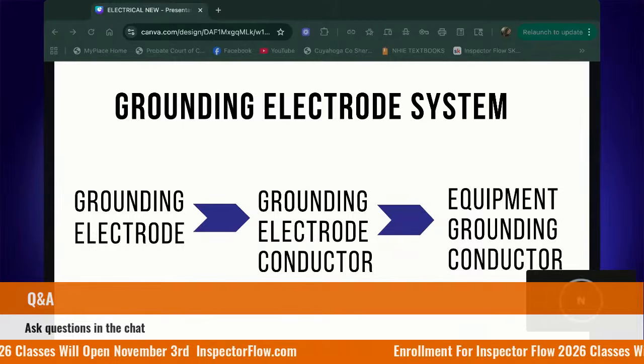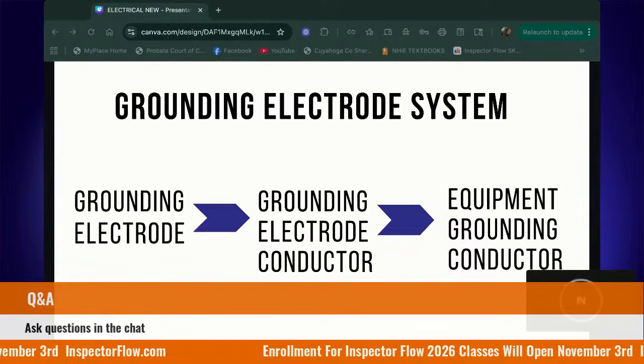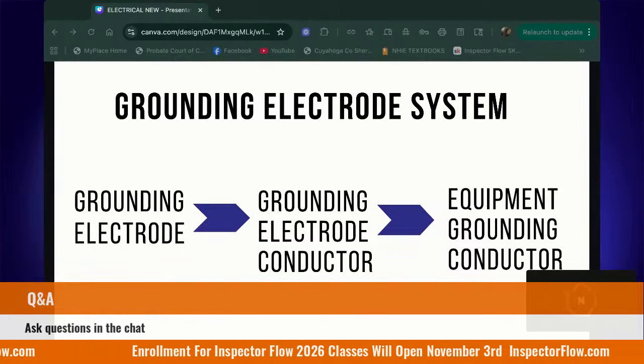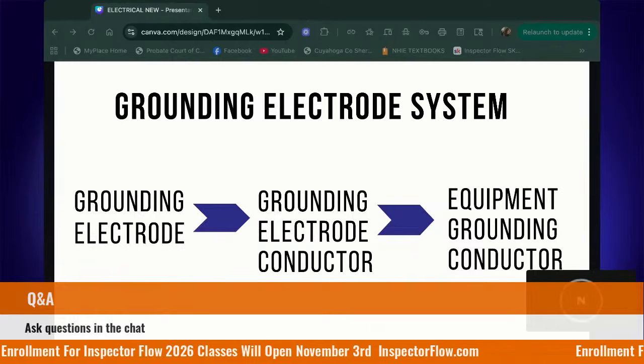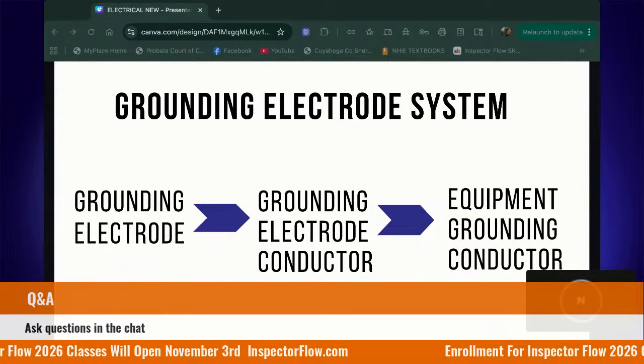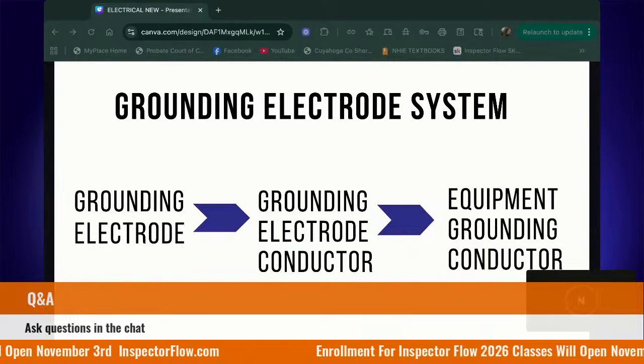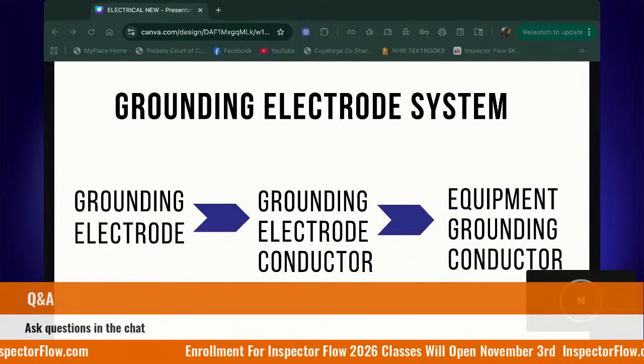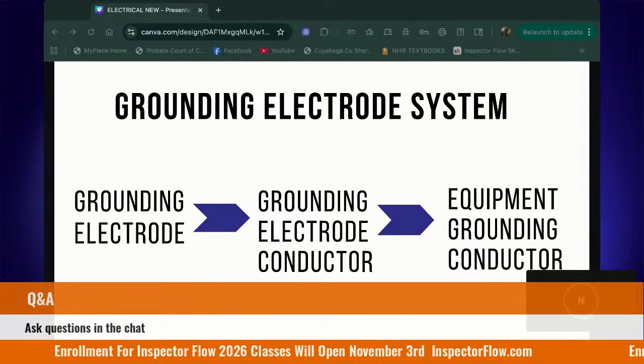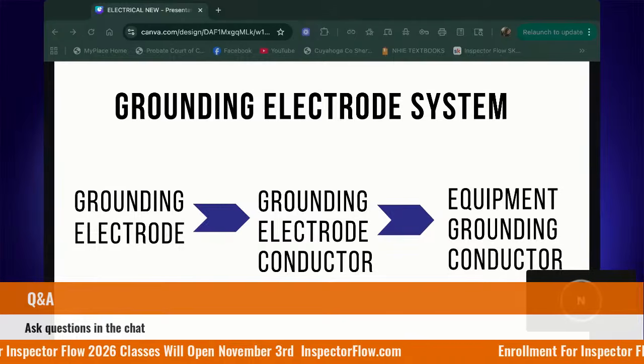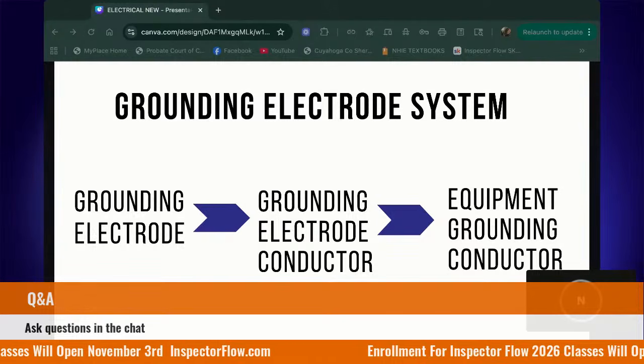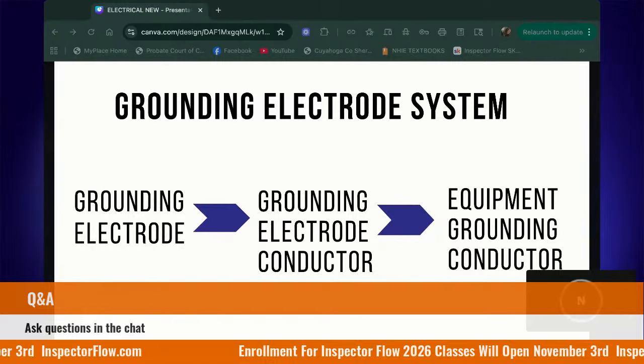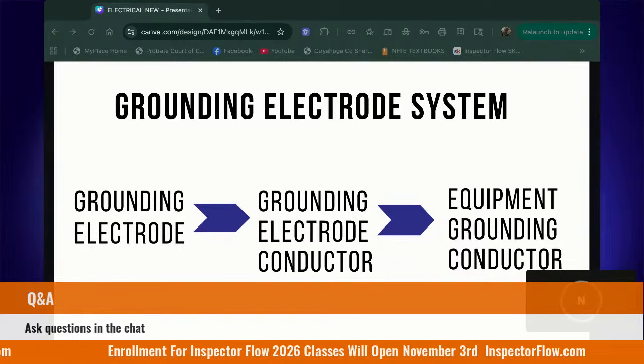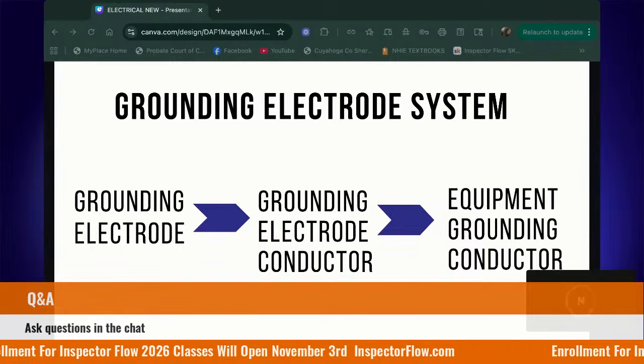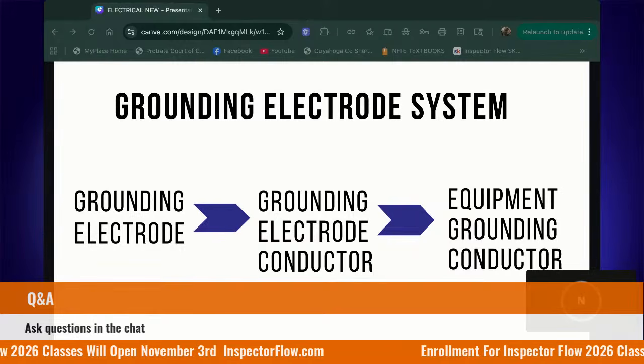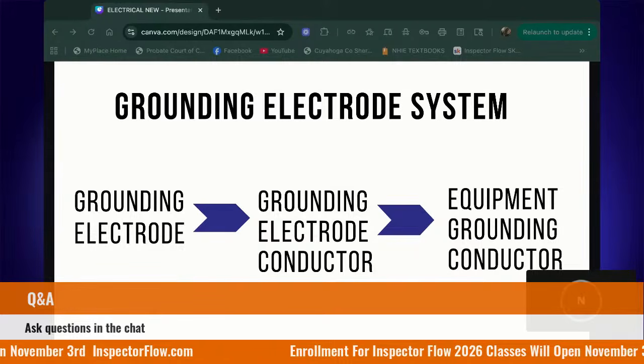Okay. Then we have the GEC, the grounding electrode conductor. This is the wire that connects the grounding electrode or the ground rod back to the neutral bar that's inside the main service panel. So this is the connection point between our panel and the grounding electrode outside, the GEC. It is a copper wire. It is typically thicker than most of the other wires that are going to be in the panel.